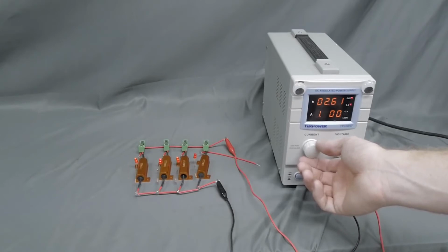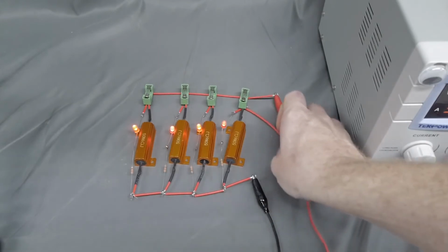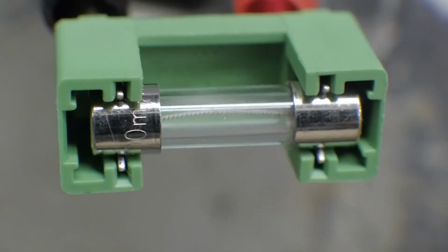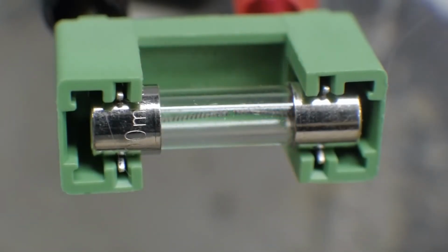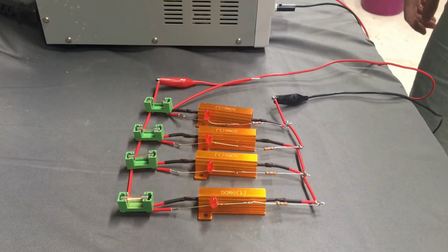show how this works. Imagine a series of interconnected transmission lines, all feeding their own service areas, represented by the power resistor and LED light in this model. During peak demand, these lines might be operating at nearly their maximum capacity. If one line experiences a fault, for example shorting out against a tree branch, protective relays will isolate the line. In my case, when I short out the line, the fuse blows. But if not handled correctly, that can mean that the entire electrical load gets automatically distributed between the remaining transmission lines, pushing them beyond their limit. All of a sudden, you have a cascading failure.